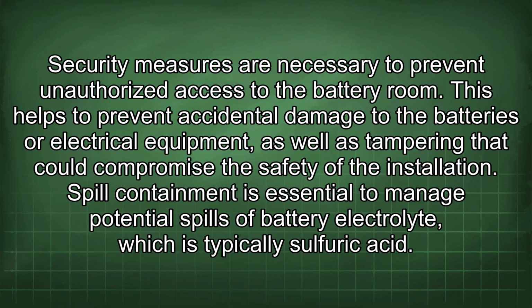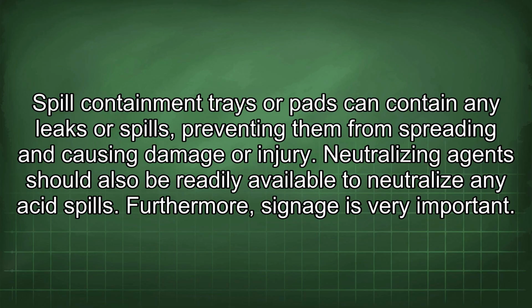Security measures are necessary to prevent unauthorized access to the battery room. This helps to prevent accidental damage to the batteries or electrical equipment, as well as tampering that could compromise the safety of the installation. Spill containment is essential to manage potential spills of battery electrolyte, which is typically sulfuric acid. Spill containment trays or pads can contain any leaks or spills, preventing them from spreading and causing damage or injury. Neutralizing agents should also be readily available to neutralize any acid spills.